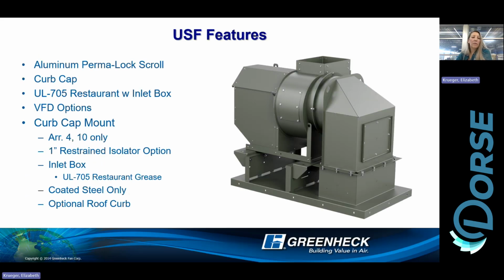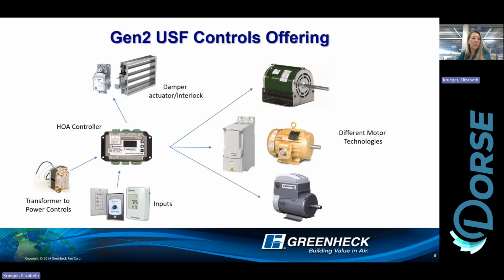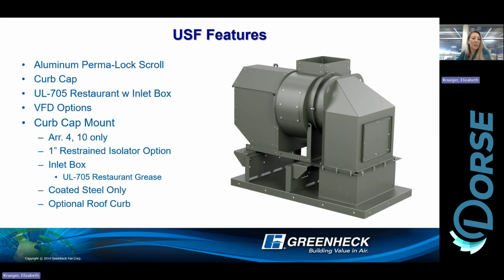We do offer our fans to be put on curbs as well. What you see here is actually an inlet box. Our contractors really tend towards the curb and curb cap applications because then they don't have to run additional ductwork into that fan. Normally we want to see like 3 wheel diameters of straight ducting leading to the inlet of the fan.